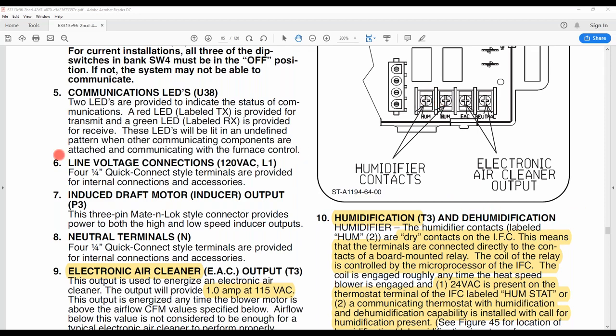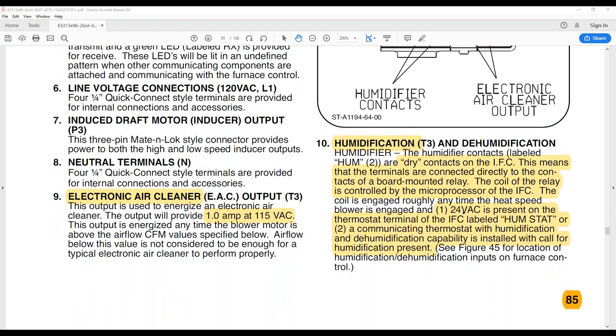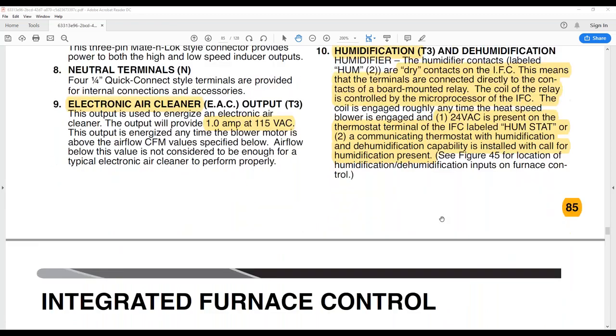You'll find that on this page towards the bottom, number 10 here with the humidification. It tells you when 24 volts is present on the thermostat terminal of the IFC labeled HumStat, it will energize those contacts and close those dry contacts. Or if you have a communicating thermostat, the communicating thermostat can close those contacts also. And we'll get down into the wiring here.